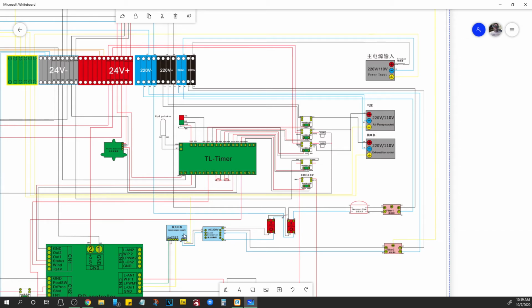Now on the ones with the chiller, your chiller is also connected to this circuit. So if you're looking for a no power issue, the main power switch can go bad. If your machine turns on but you can't fire the laser and/or you don't have chiller power, it's likely this laser power switch, because that carries both on the ones where the chiller is in.